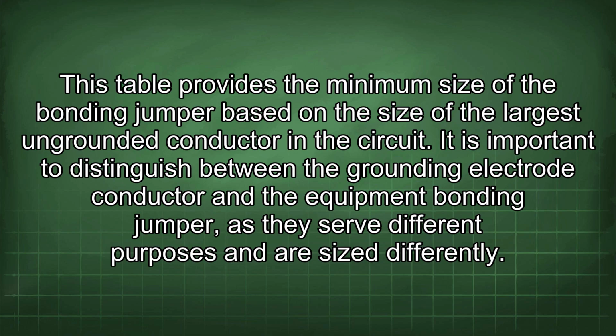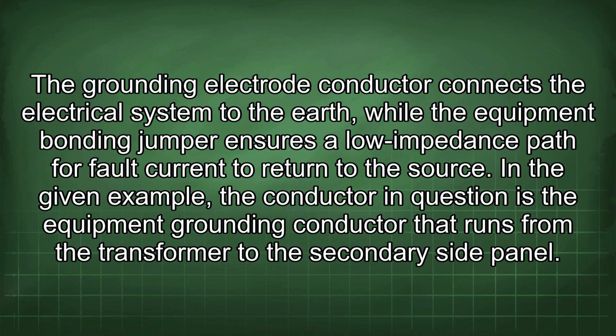in the circuit. It is important to distinguish between the grounding electrode conductor and the equipment bonding jumper, as they serve different purposes and are sized differently. The grounding electrode conductor connects the electrical system to the earth, while the equipment bonding jumper ensures a low impedance path for fault current to return to the source.